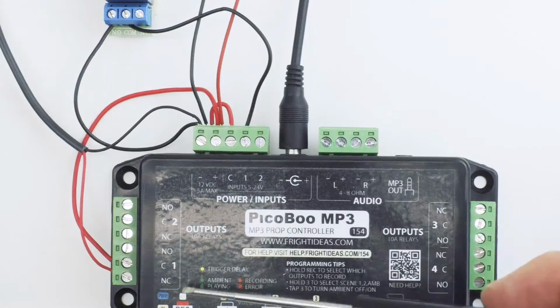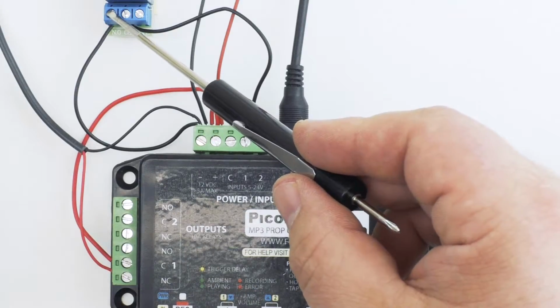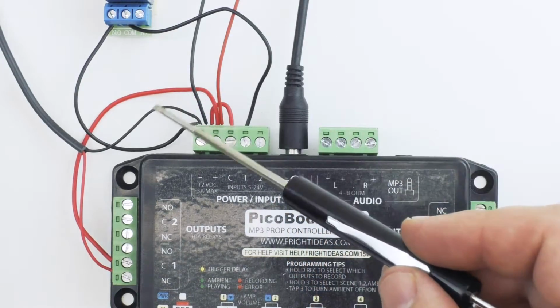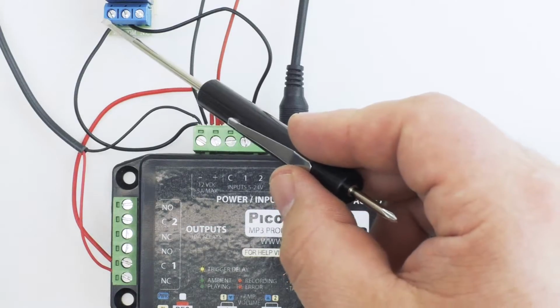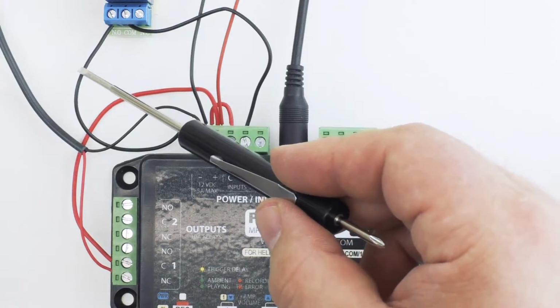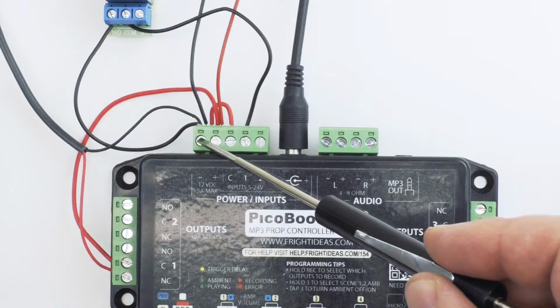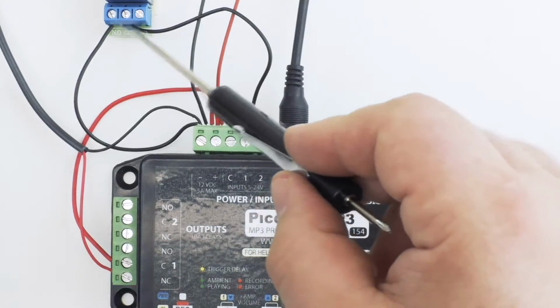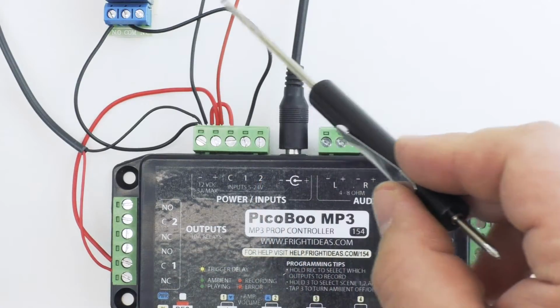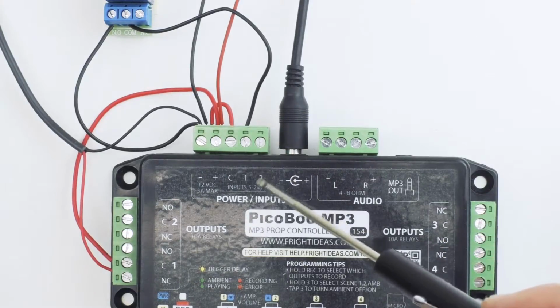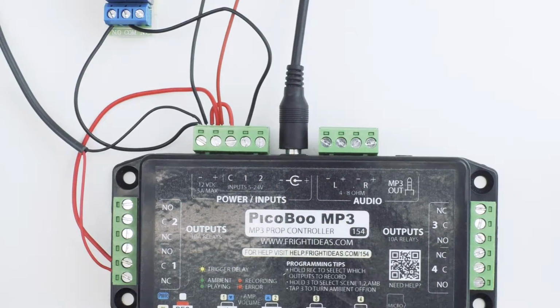You can see here that just like the output relay, there are three terminals, NO, C, and NC. We're using the normally open terminal, so we have one wire coming from the normally open terminal going into the negative terminal of our power. The other wire on the relay goes from the common over to the number one input on our trigger inputs.